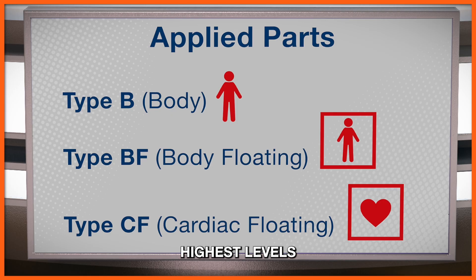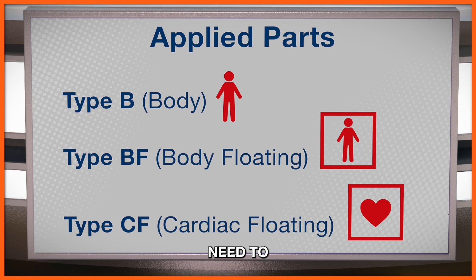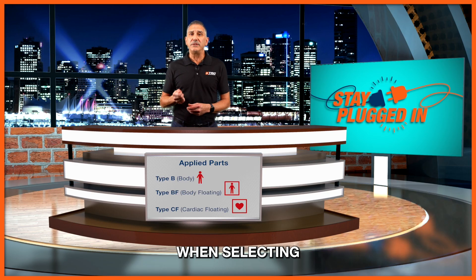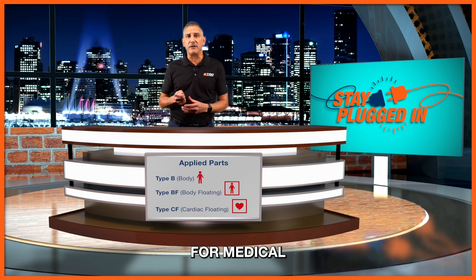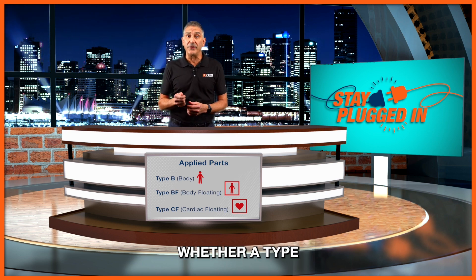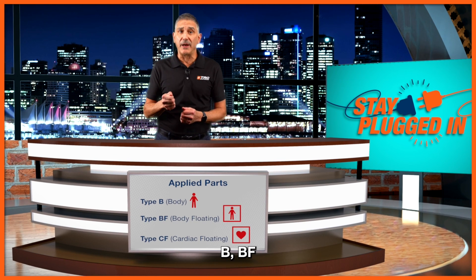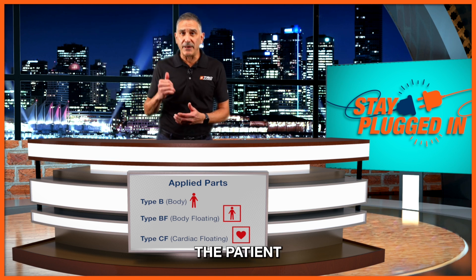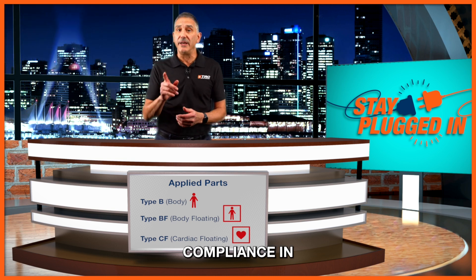In order to ensure that the highest levels of safety are met, the power supplies used in various medical applications need to be compliant with various standards and regulations. The key parameter is the suitability of a power supply for use in a type B, BF, or CF application. When selecting power supplies for medical applications, it is critical to understand whether a type B, BF, or CF suitable power supply is necessary to ensure patient safety and compliance in your region.